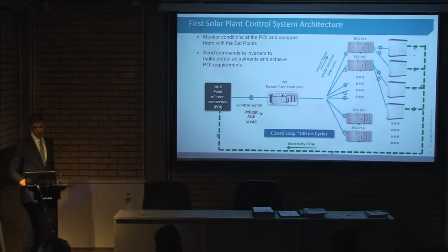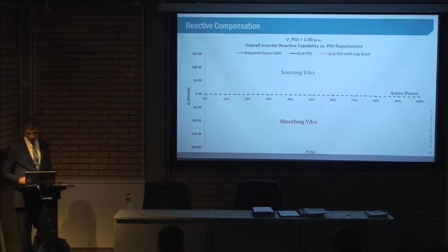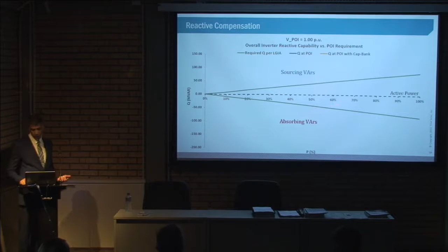Combining inverters with a power plant controller and a capacitor bank gives you a device similar to a StatCom — not exactly the same — allowing us to provide grid support without spending too much money. Here you can see the typical curve for a utility company's reactive power requirements for generators, and this is a typical curve for an inverter.